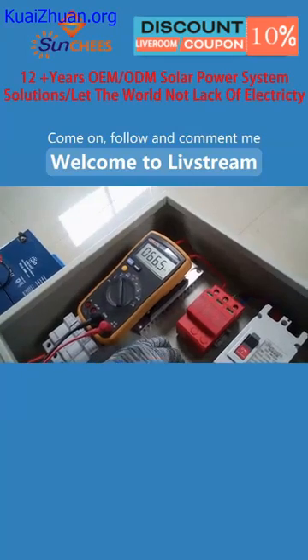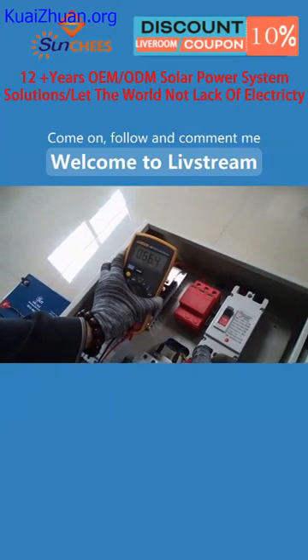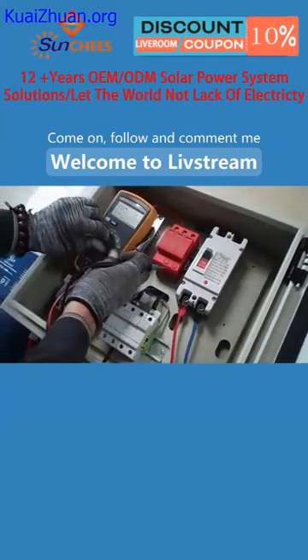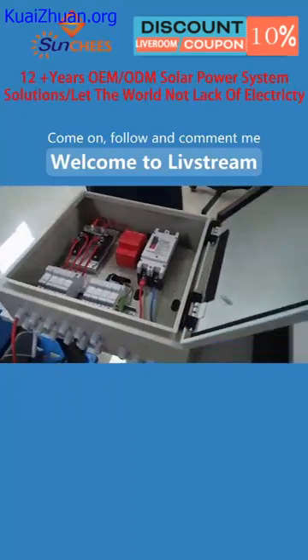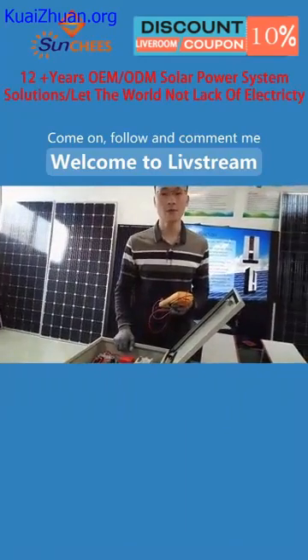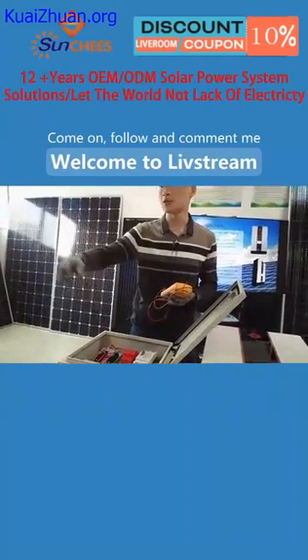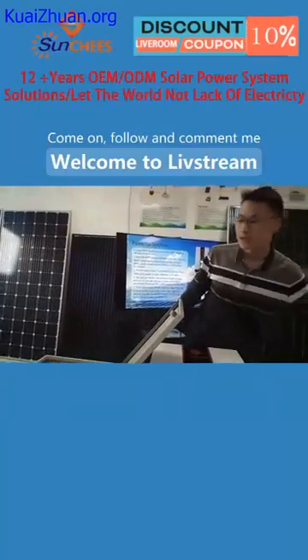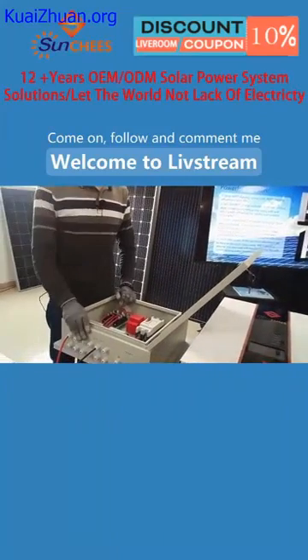You can see now the PV array voltage is 66.4 volt DC. That means it is normal. The connection in the above steps is correct. Because for two pieces of 350 watt solar panels, the one piece voltage will be around 36 volt, and two pieces in series connection the voltage will be around 70 volt DC. But the solar panels are installed inside the building in our showroom. The sunshine cannot come inside, so if two pieces of solar panels are in series connection, the voltage can reach 66 volt. It is normal. That means we have already connected the PV combiner and PV array correctly.